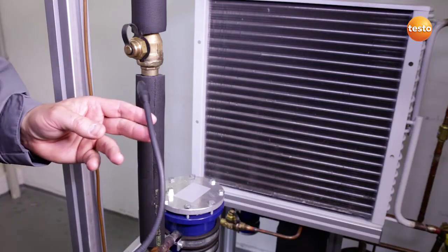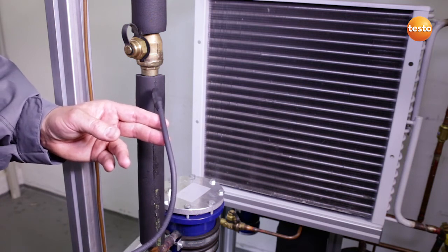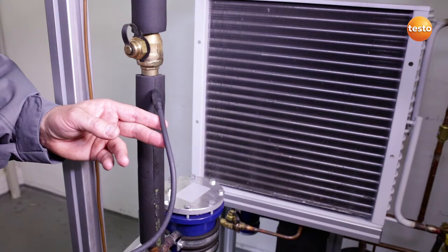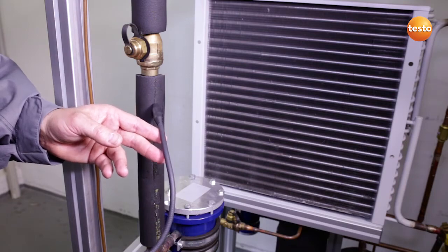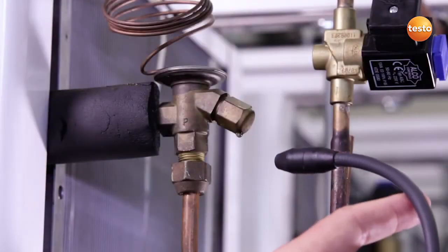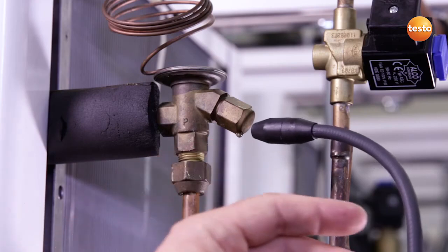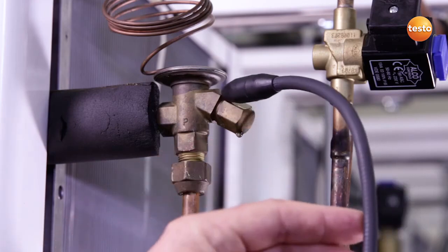Freshly glued insulation hoses on refrigeration pipes can be sources of false interpretation. As you can see clearly here, possible contamination of the sensors, such as here by this water drop, can seriously influence the sensitivity of the sensor.